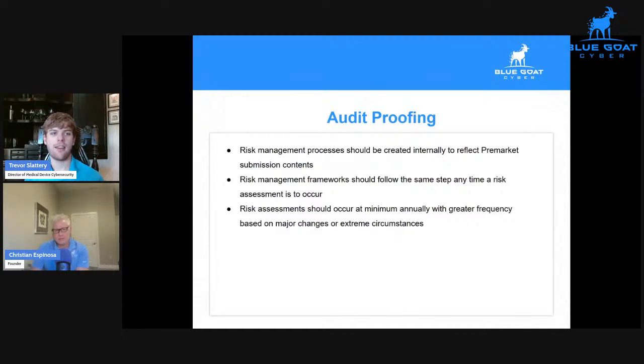If we're switching out one Bluetooth library for another, and it doesn't change the operation of the device, usually that's not going to be a major change. We'd still want to track that. We want to evaluate it through supply chain security considerations, but it's not going to require a full new risk assessment, new penetration testing, all of that.